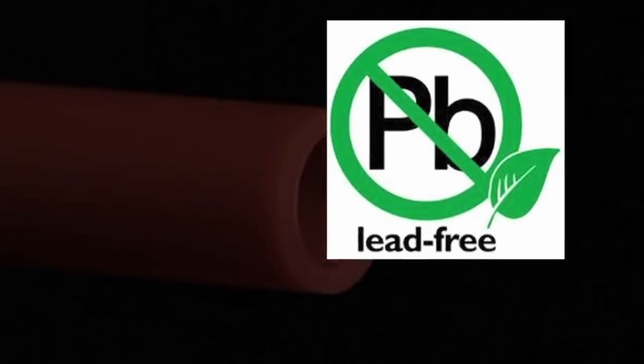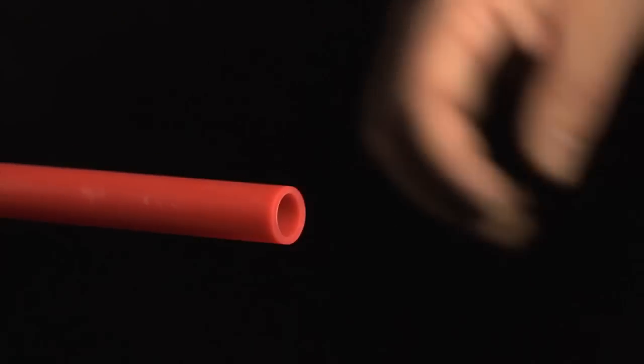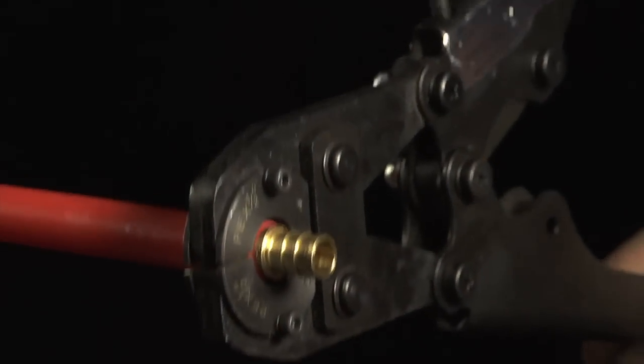Barb PEX fittings are attached to PEX with a crimp ring or pinch clamp. Slide the ring or clamp over the end of the tubing. Insert the fitting into the tubing. Move the ring or clamp until it's one-eighth to one-quarter inch from the end of the tubing.